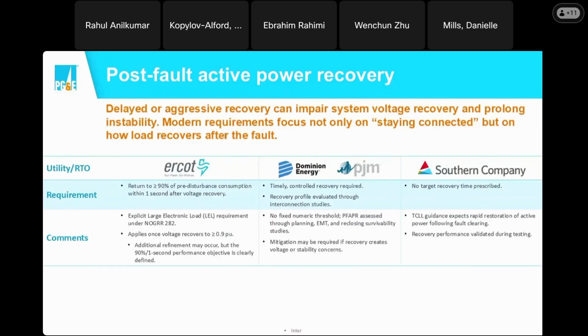One is what really happens if there is an excessively delayed recovery, which would traditionally prolong the depressed voltage condition and would likely impede restoration as well. And then what happens if you have an aggressive step recovery, which can really increase the reactive demand very abruptly and also delay voltage stabilization depending on what part of the system you're operating in.